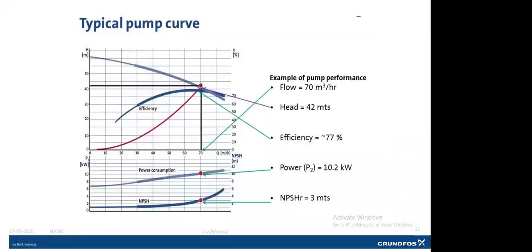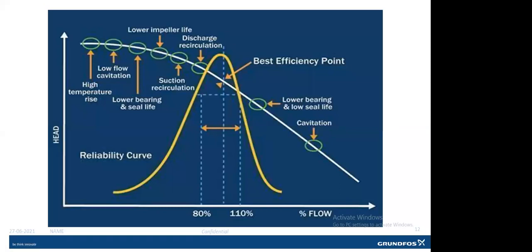Now we've seen the QH curve, and we will see the impact if the duty point shifts from the best efficiency point, and what it impacts on the pump performance. If the duty point shifts to the left-hand side of the curve, or we can say the pump operates at lower flow and higher head than the design, there are effects on the pump like lower impeller life, discharge recirculation, suction recirculation, and lower bearing and seal life, because we are operating the pump near the shut-off condition. Our pump tends to run in churning condition unless it is equipped with a VFD.